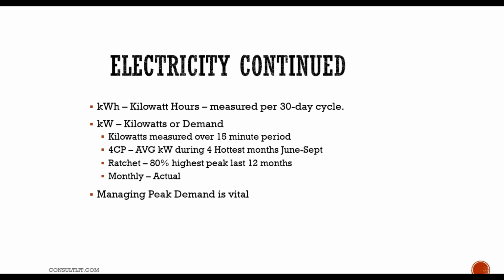But two things I want you to walk away with are what kilowatt hours are and what kilowatts are. Kilowatt hours is basically the kilowatts measured over a 30-day cycle. It's the consumption, or the amount of energy you use during the 30-day period. Kilowatts is the rate at which you use electricity. For example, if I had a 2 horsepower motor versus a 10 horsepower motor, and they both used 1,000 kilowatt hours, they're both going to use the same amount of consumption, but the rate at which the 10 horsepower uses is a lot faster than the 2 horsepower motor, if that makes sense. So the utility company is going to charge and pass forward the rate at which you use energy, and they measure that in something we call kilowatts, or demand.